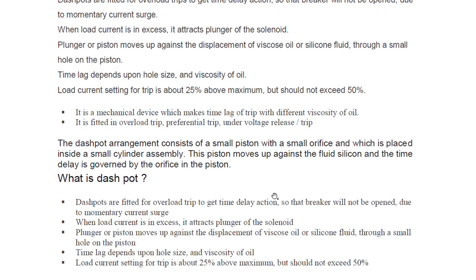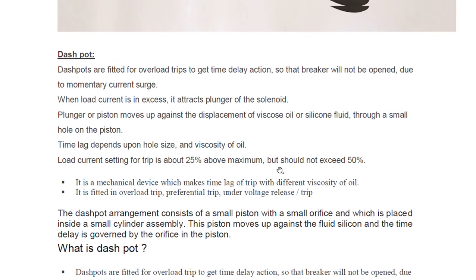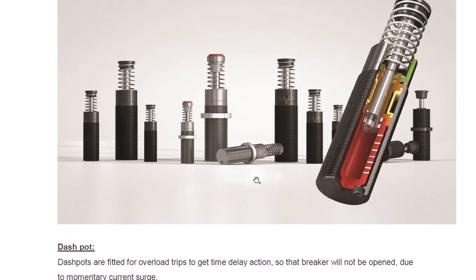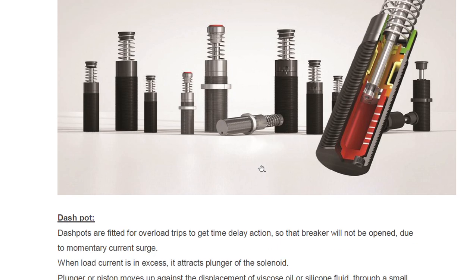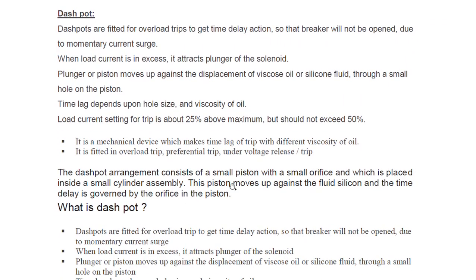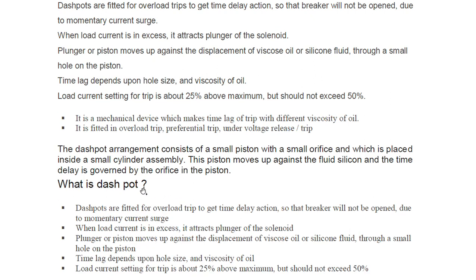The dashpot arrangement consists of a small piston with a small orifice, which is placed inside a small cylinder assembly — as you can see in the diagram. The small piston is placed inside the cylinder assembly with a small hole, filled with silicone oil. Depending on the viscosity of the oil, the piston moves up against the fluid, and the time delay is governed by the orifice in the piston.